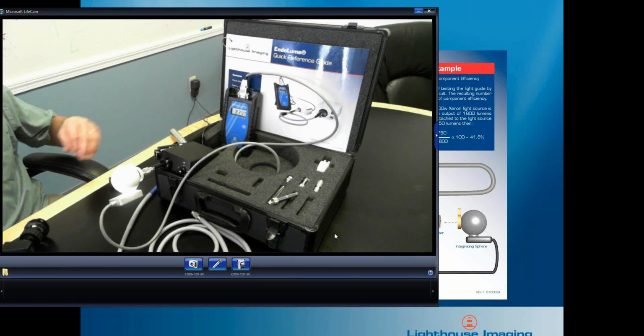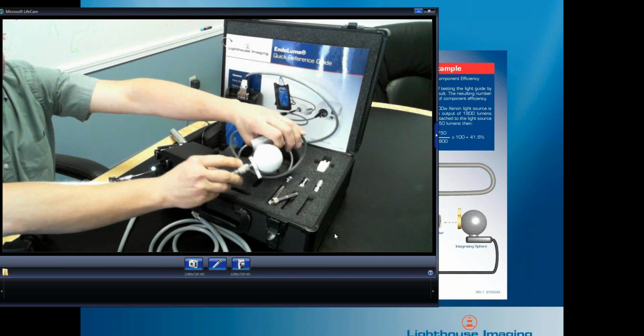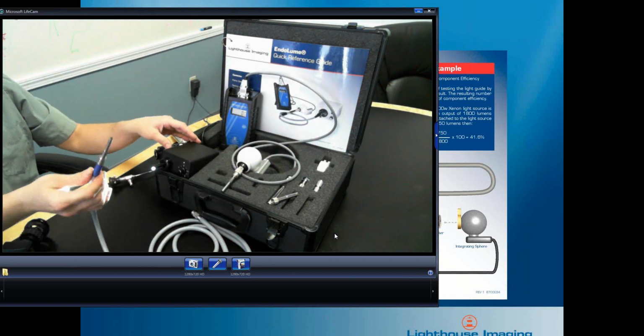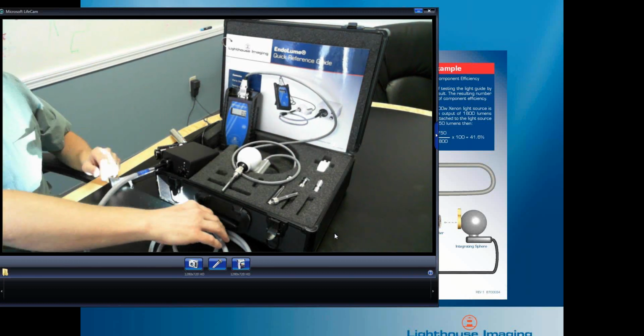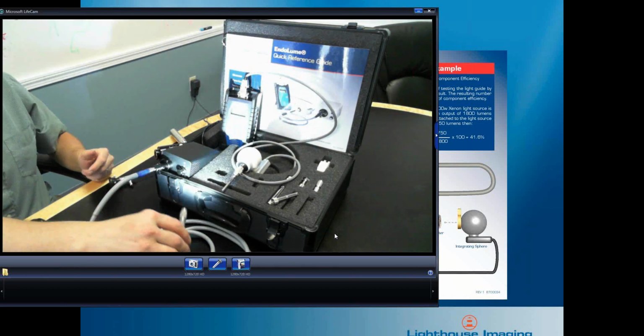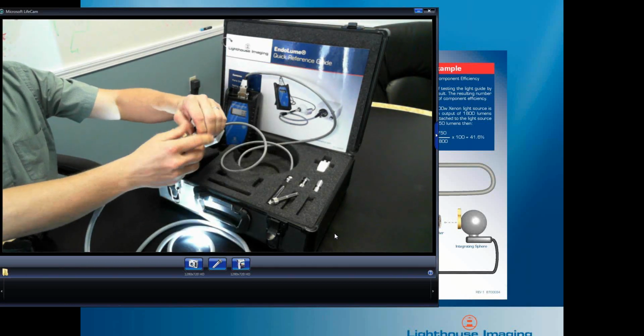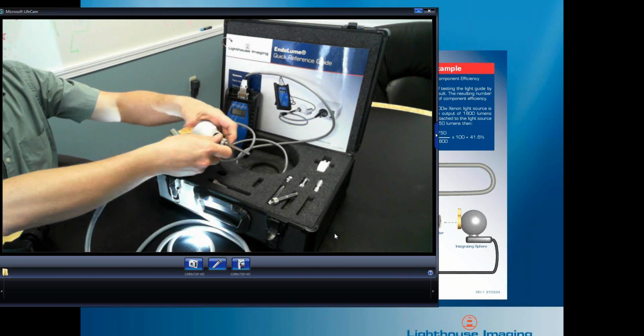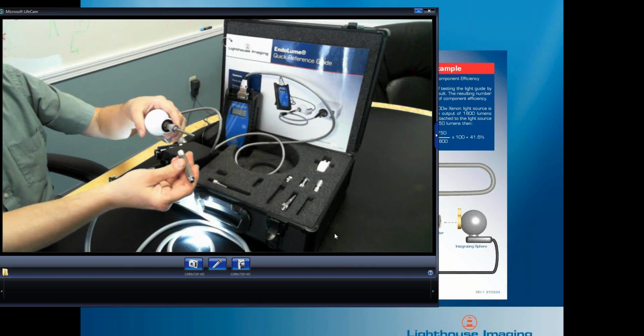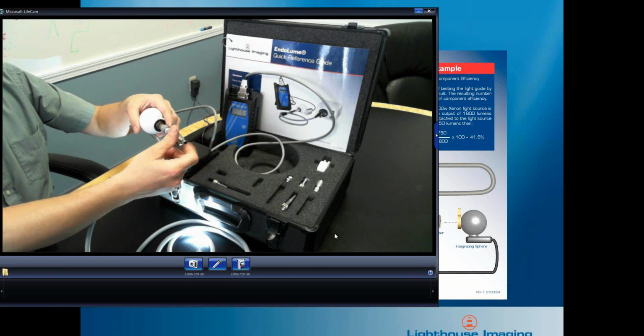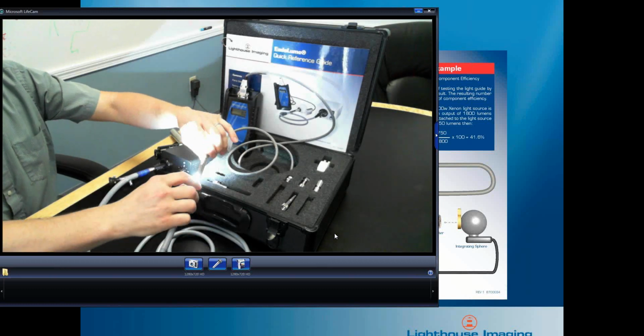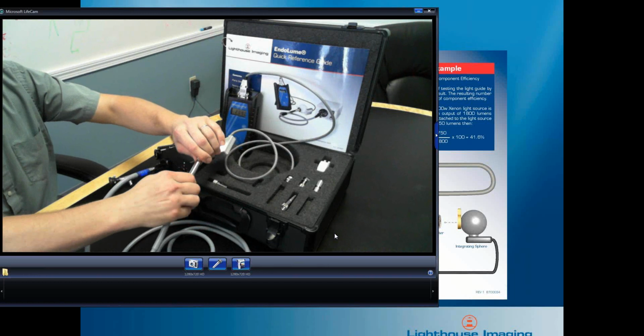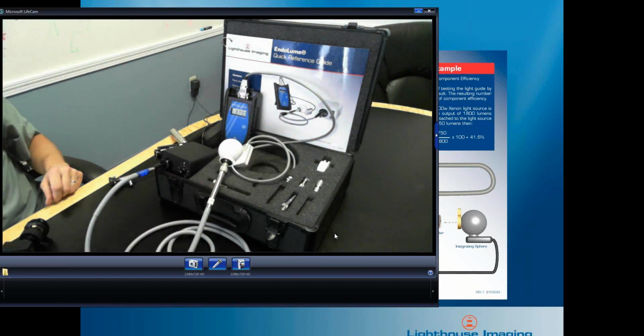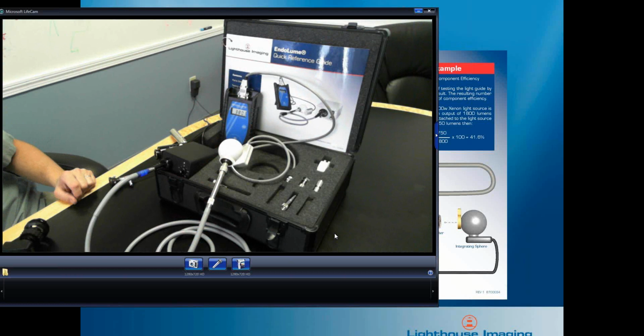So I will switch back to the live view here, and we'll take the fitting out, and now we'll hook the fiber optic cable into the light source. So now we see the light coming out of the cable. We'll change the fitting on the light optical bridge to be the correct fitting for this Storz cable, and just thread that on. And then we'll thread the end of the cable onto the fitting. So now we see that we're getting about 380 lumens out of the light cable.